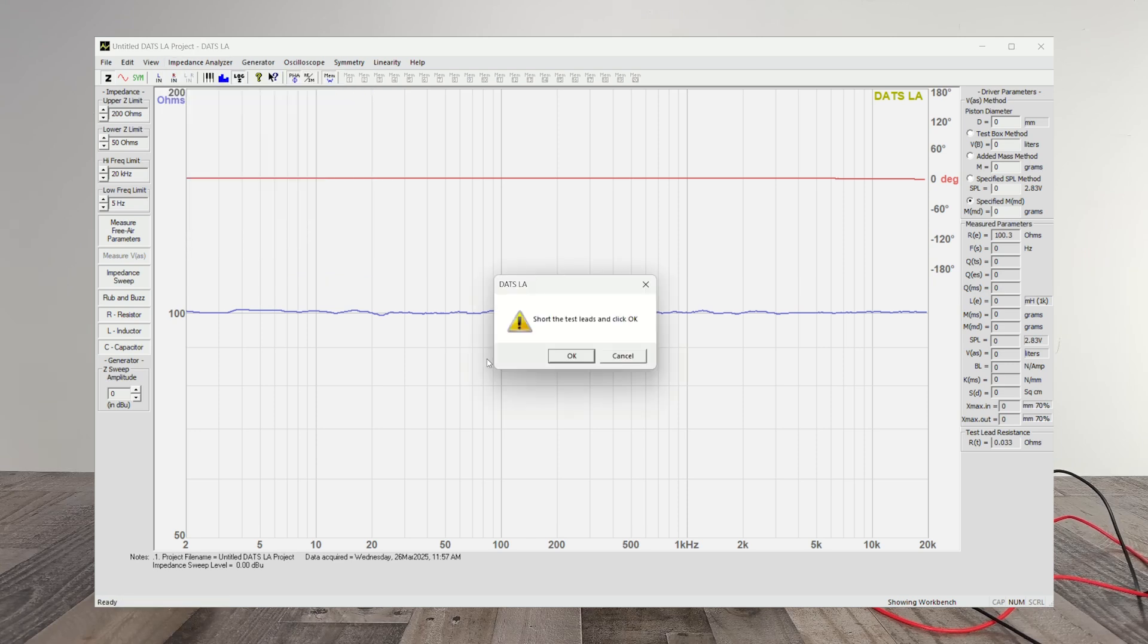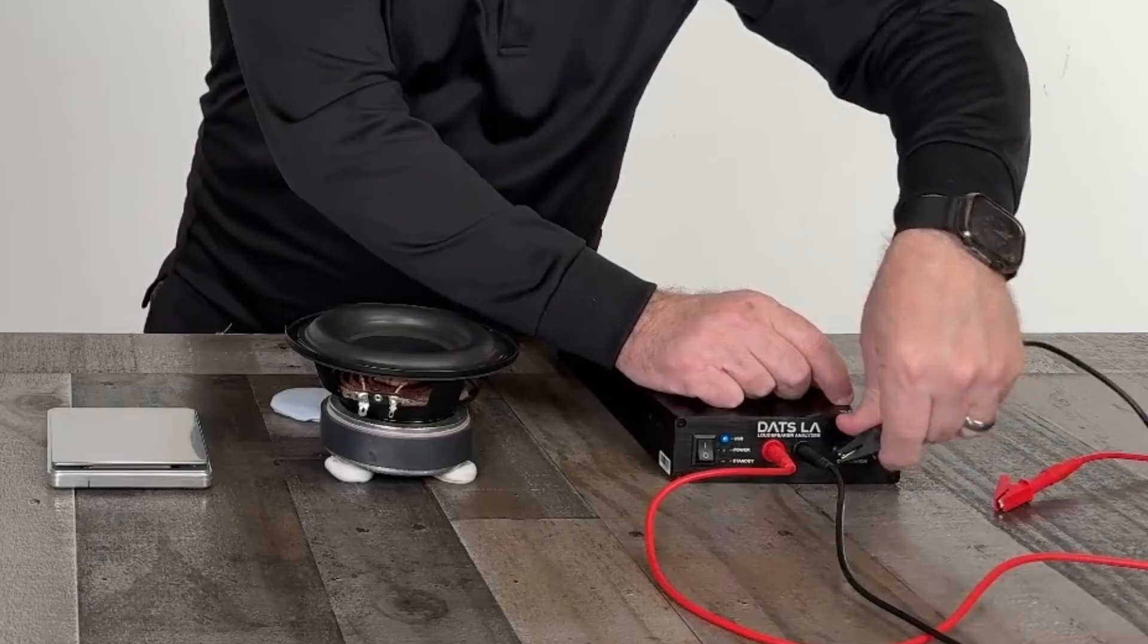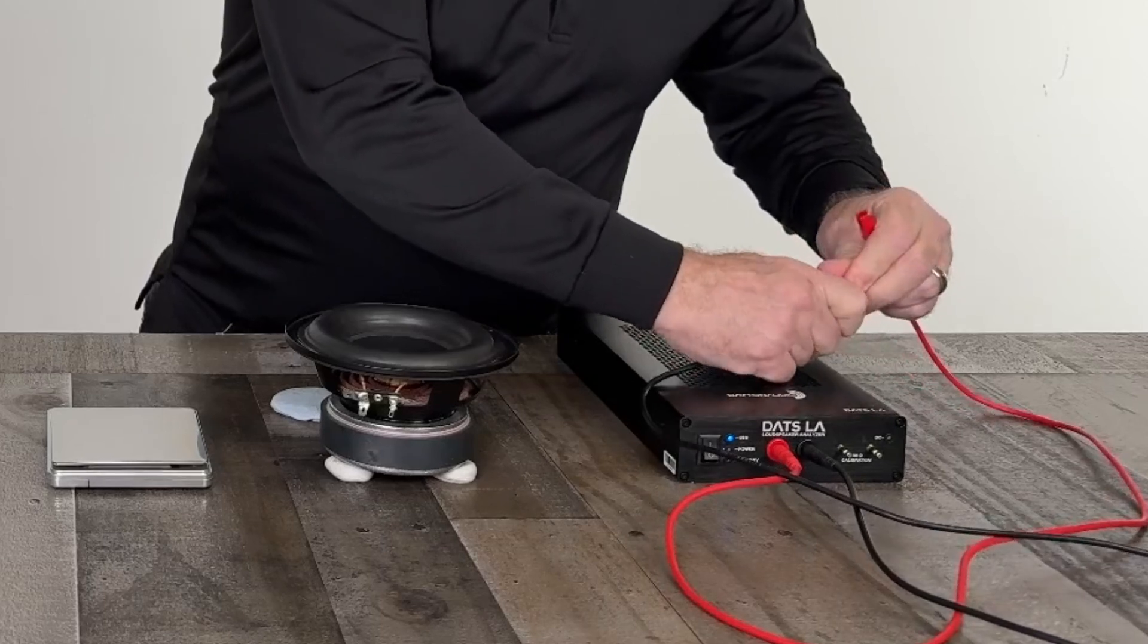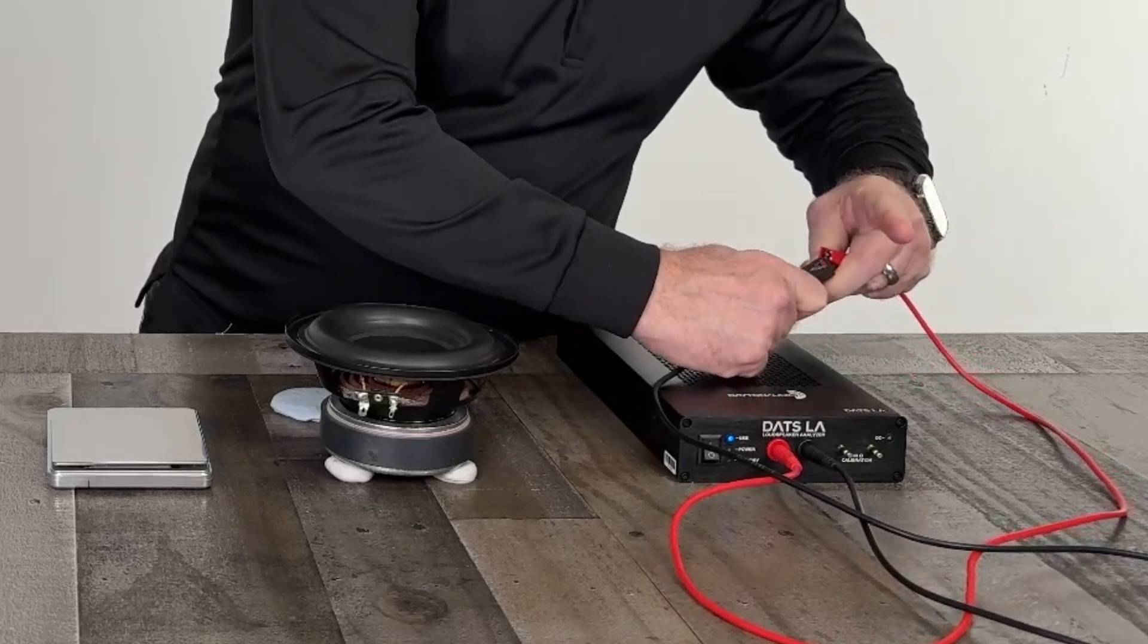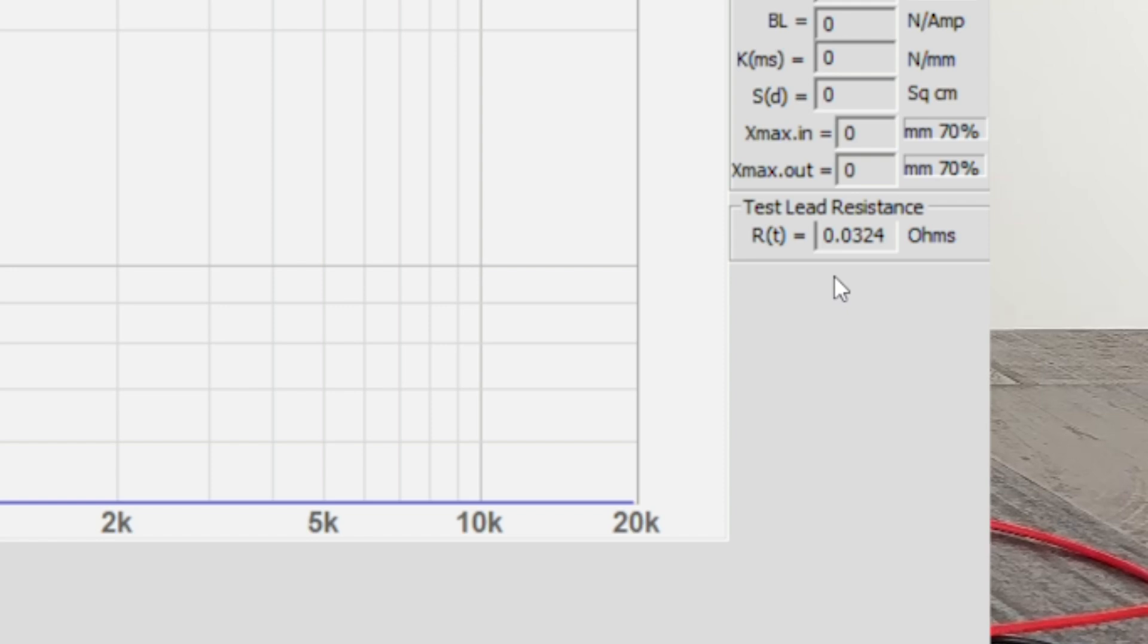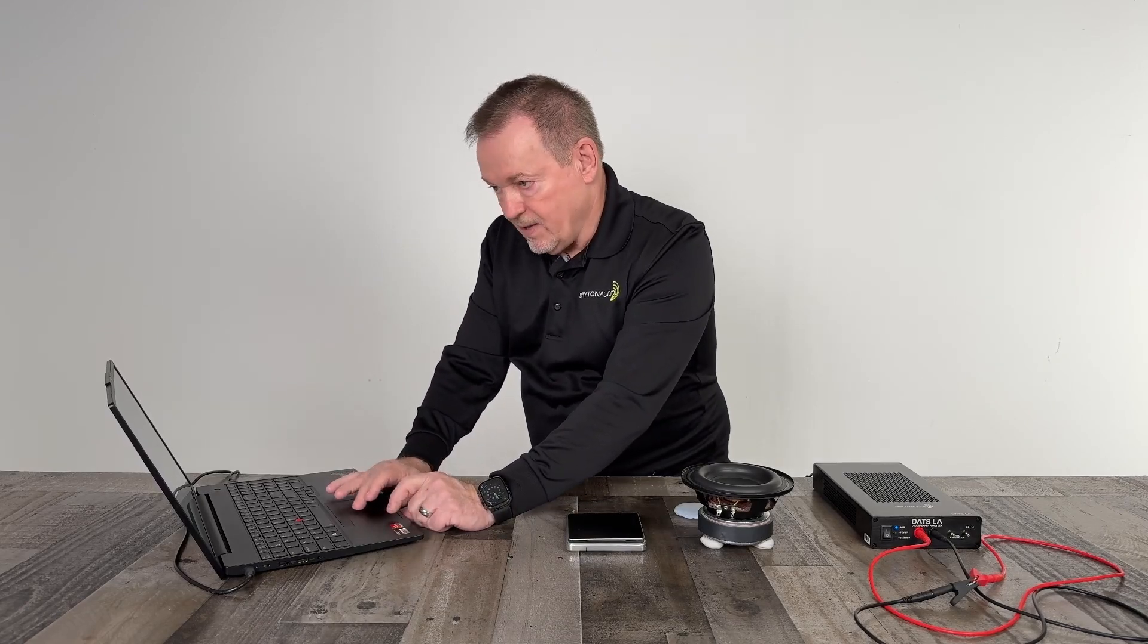So now we go to test lead calibrations. Of course, we need to connect the test leads together. These alligator clips are a little taut, which is a good thing. OK, now we have shorted the test leads together, and we say OK. Now that calibration is going to be shown as 0.032 of an ohm calibration. Anything under one tenth of an ohm would be valid.